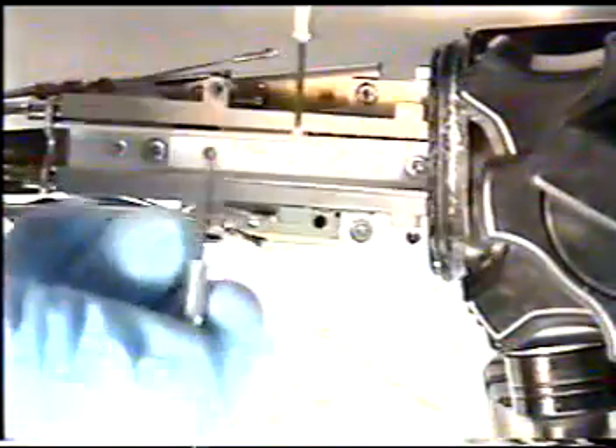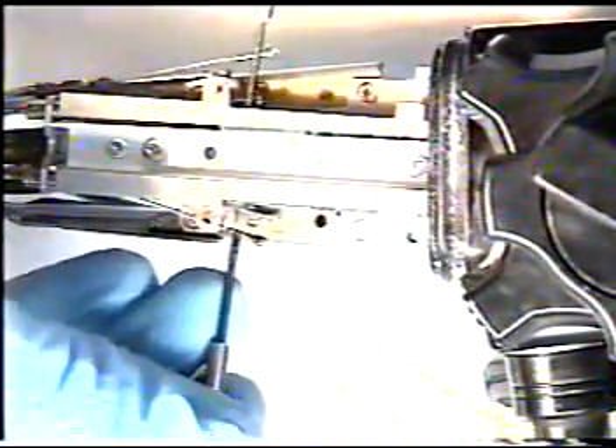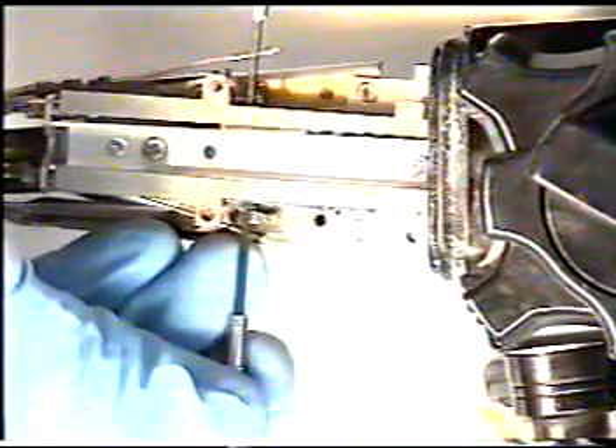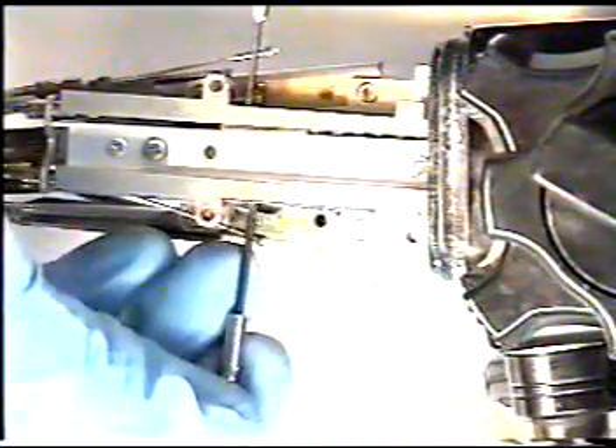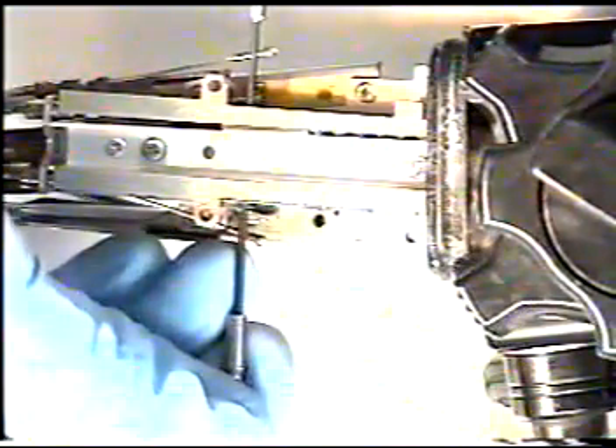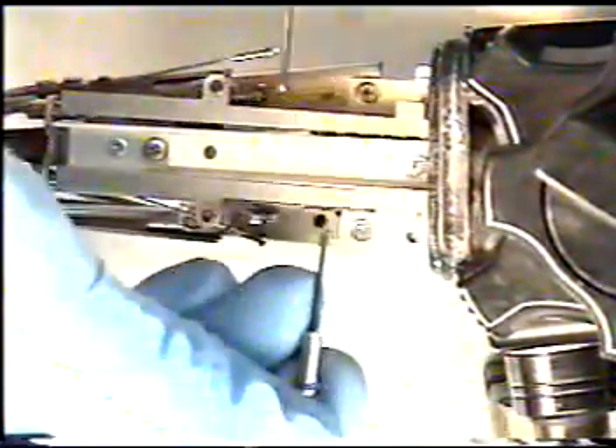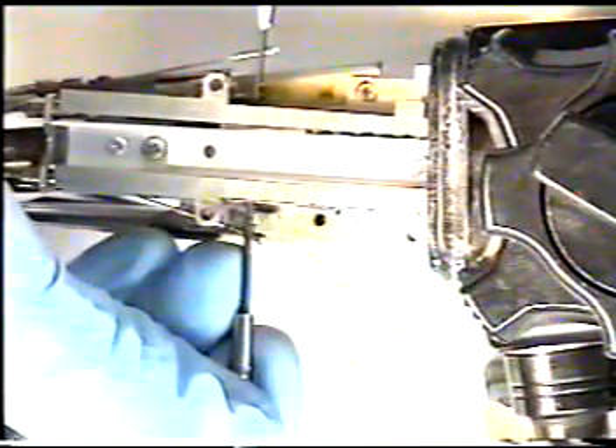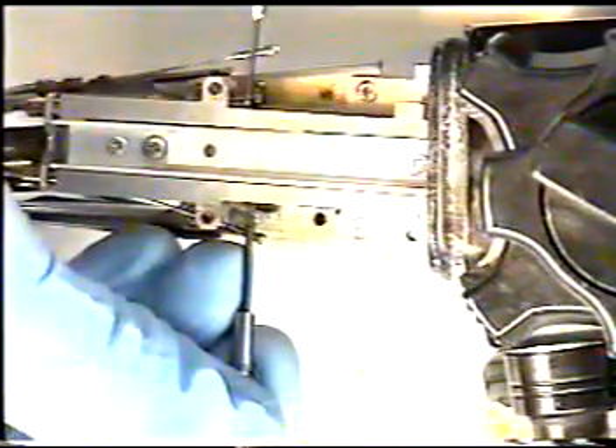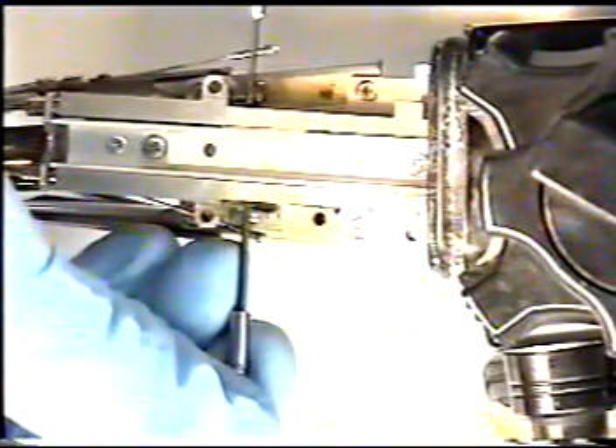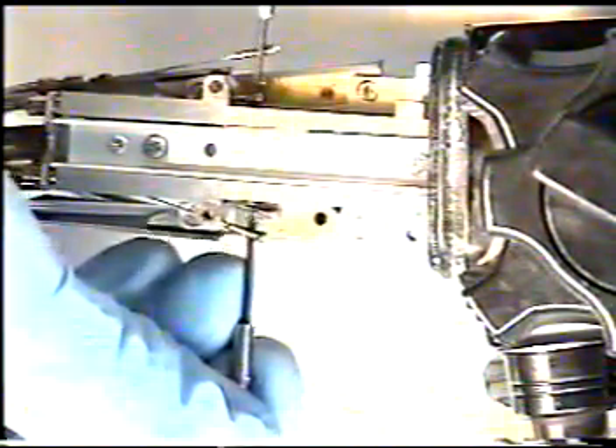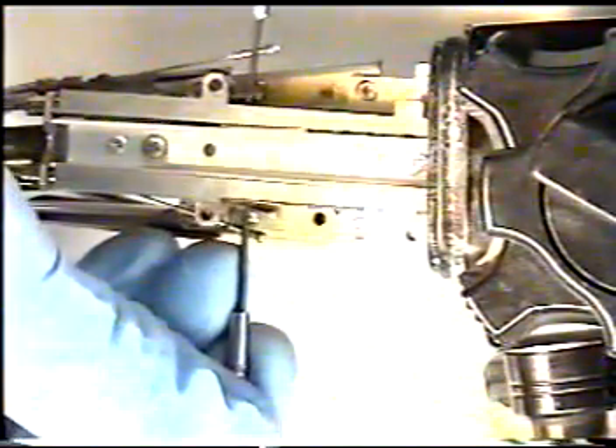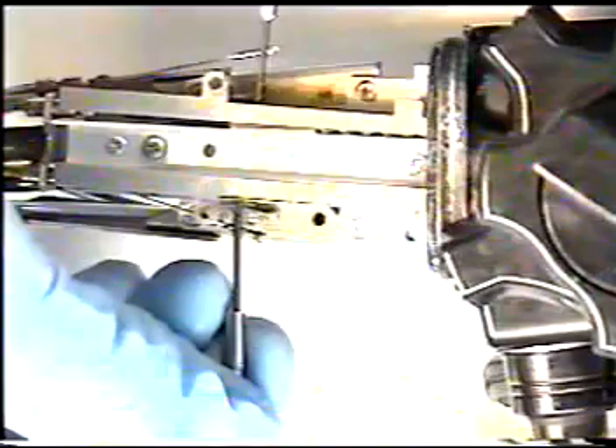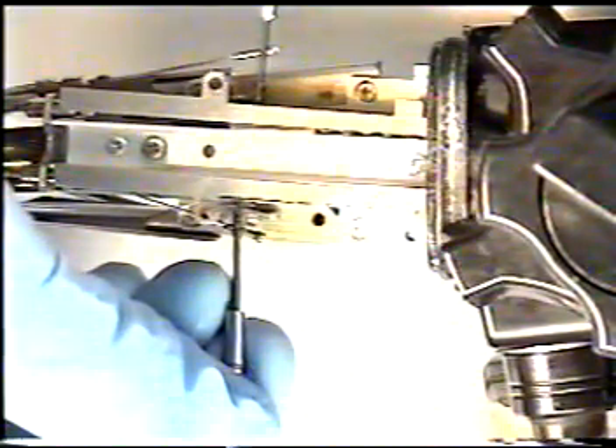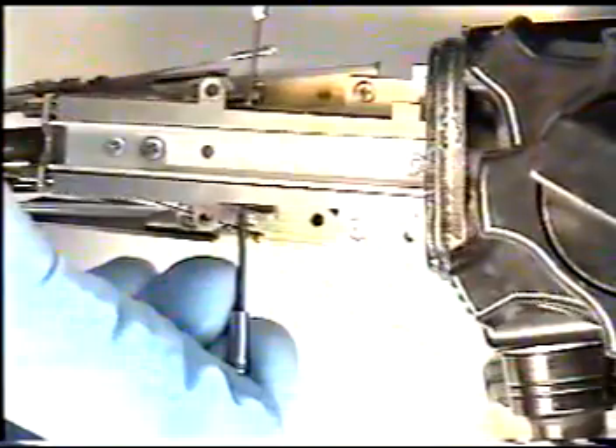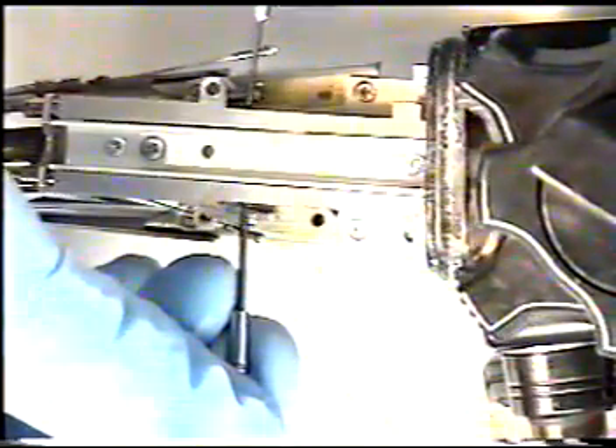working area, take your two number 2 screwdrivers and put them behind the head of each control block chain assembly. The two screwdrivers should be exactly across from each other, pulling down the chain for proper play adjustment. Do this for both the up, down, and the left, right. If one of these blocks is off or misadjusted, it will cause problems during your angulation and play adjustments. Again, be sure that these blocks meet.